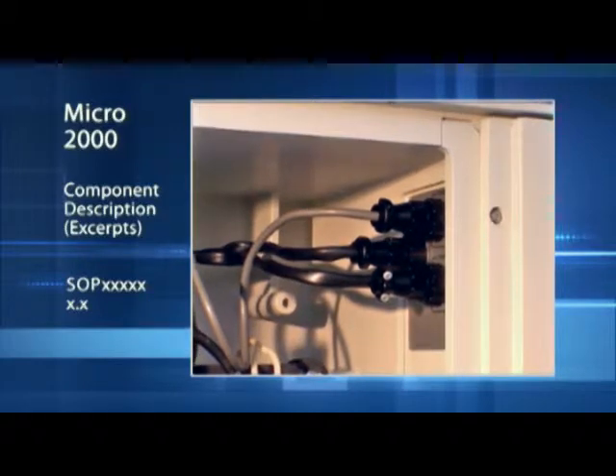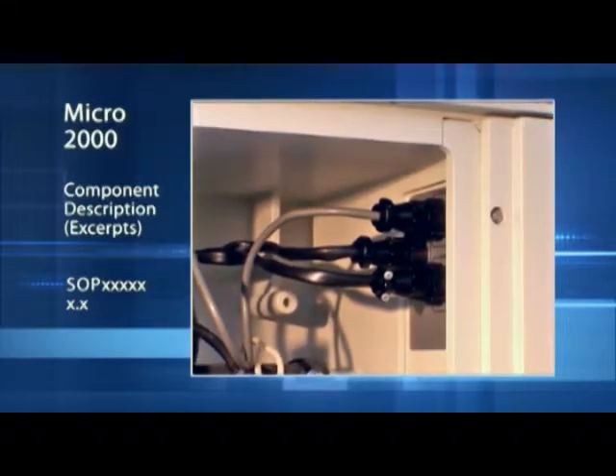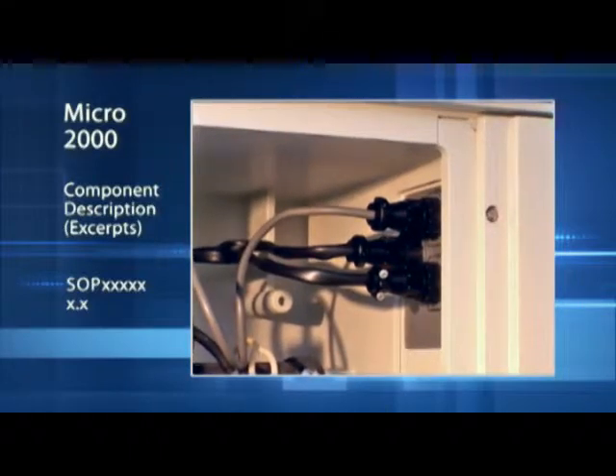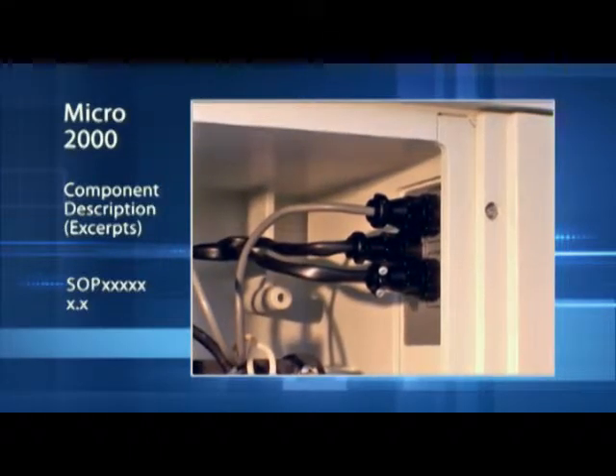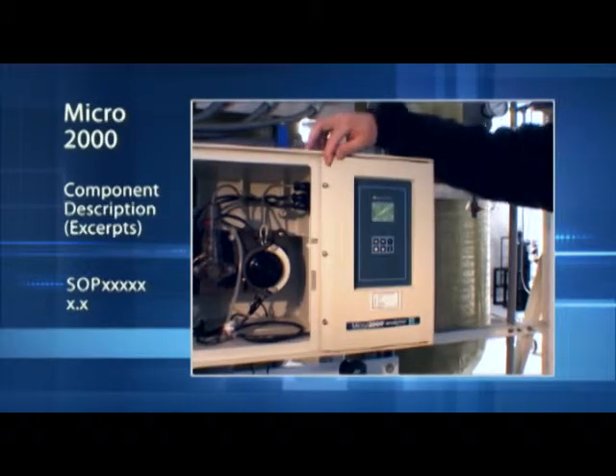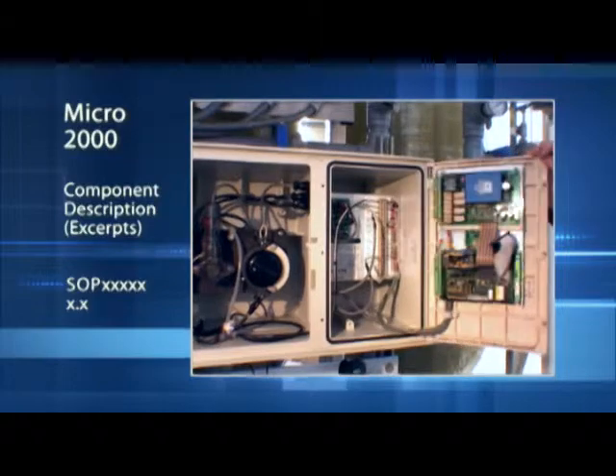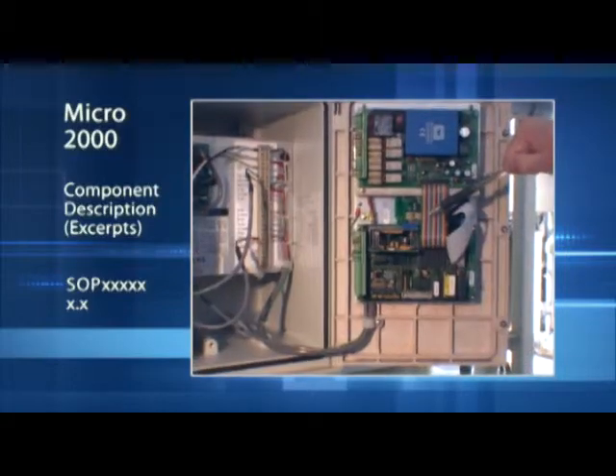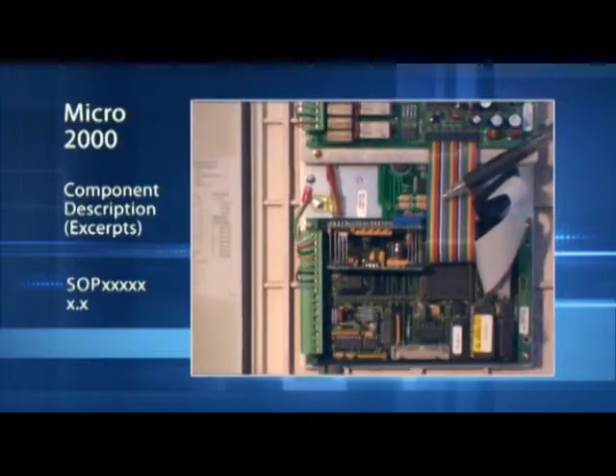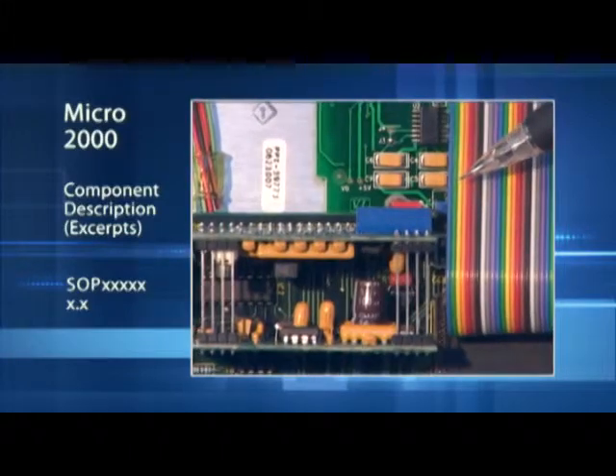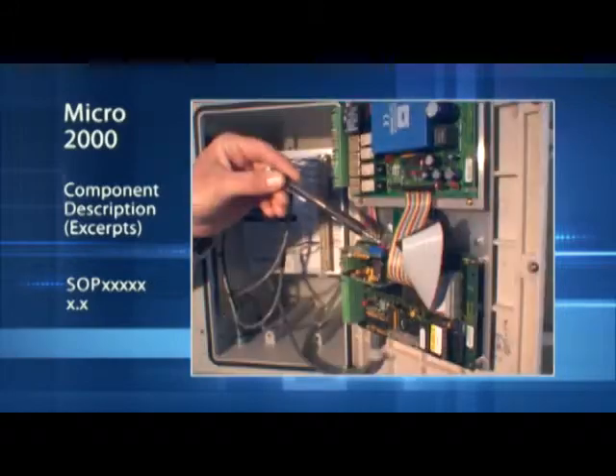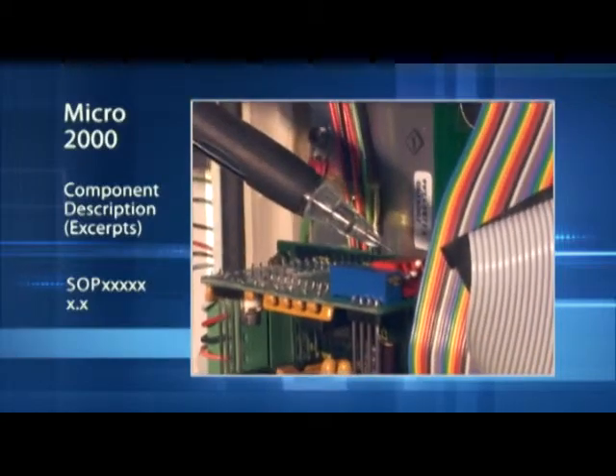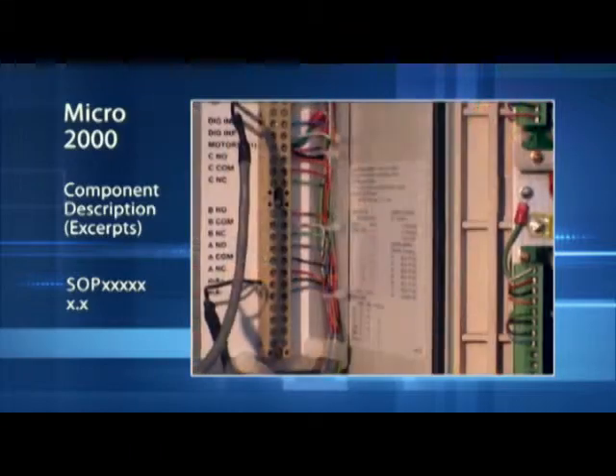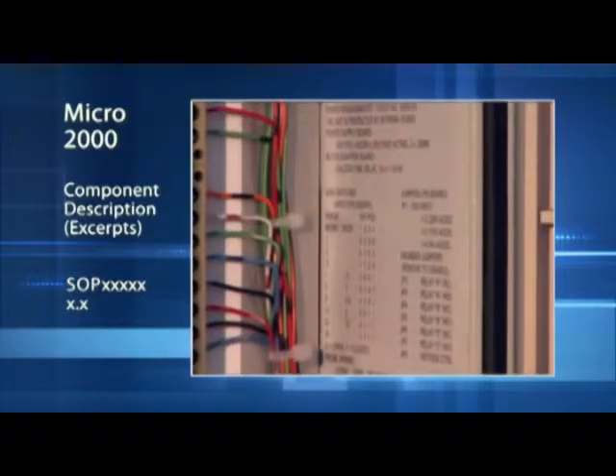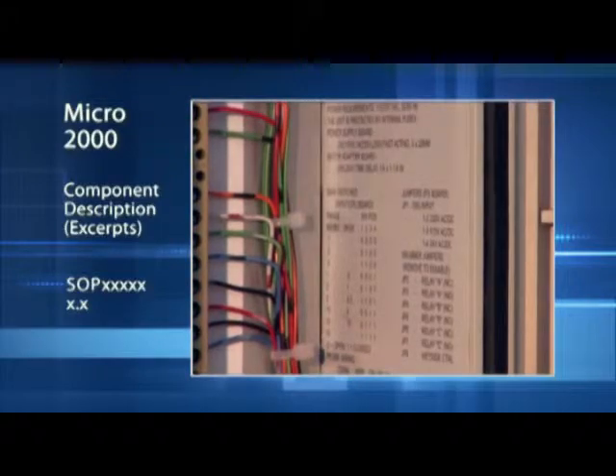They're all basically power and electronic connections for the devices and connect to the electronic panel, which is located behind the keypad section. Now we'll look inside the panel behind the keypad to see a few key features. The first thing that is an important feature to look at is to ensure that the dip switch positions are in the appropriate range for the instrument. On the inside of the panel, there's a sticker, and in the owner's manual, that tells you what positions the switches need to be in for which range.